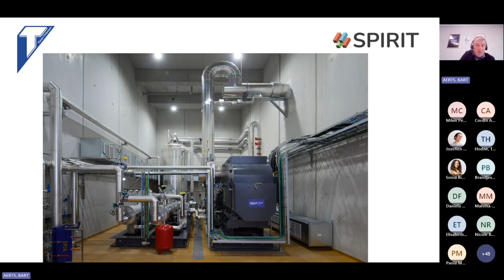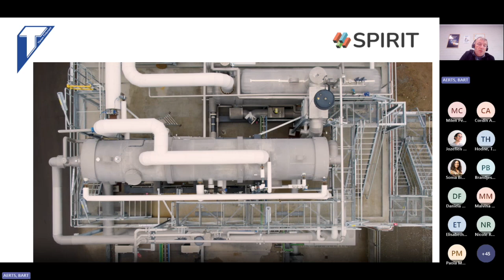This is a top view, drone view, of the heaters. Another aspect is that the heaters work with a quite small delta T, so the installation for a 4 megawatt heat pump is quite big. This is also because we have steam with other components in it, so we use shell-and-tube heat exchangers, which are a bit bigger than standard plate heat exchangers. This is a side view of the installation.